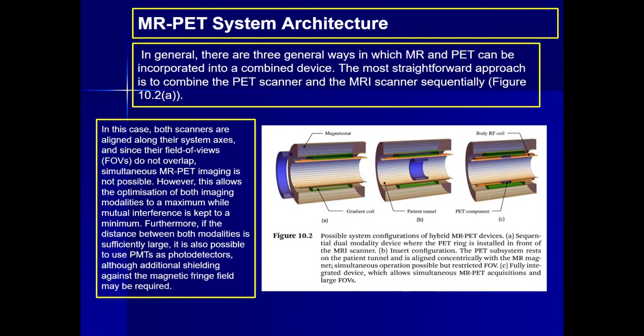MR-PET system architecture. In general, there are three general ways in which MR and PET can be incorporated in a combined device. The most straightforward approach is to combine the PET scanner and the MR scanner sequentially. This is the diagram: here is the PET, here is the MR. In this case, both scanners are aligned along their system axis, and since their fields of view do not overlap, simultaneous MR-PET imaging is not possible.